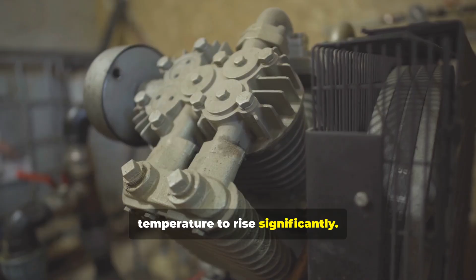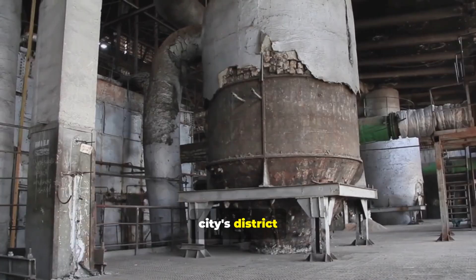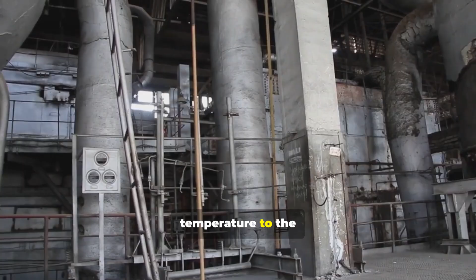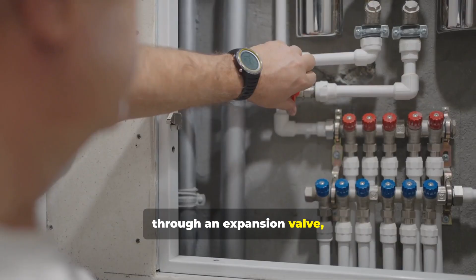It is now hot enough to be used for the district heating network, representing a major upgrade in thermal quality. The hot refrigerant gas is then passed through a second heat exchanger. On the other side of this exchanger flows the cold water returning from the city's district heating network. The intense heat from the refrigerant transfers to this water, raising its temperature to the required level for urban heating. As it gives up its heat, the refrigerant gas cools and condenses back into a liquid. This high-pressure liquid then passes through an expansion valve, where its pressure and temperature drop, returning it to its initial state, ready to begin the cycle all over again. This continuous process efficiently multiplies the value of the original waste heat.